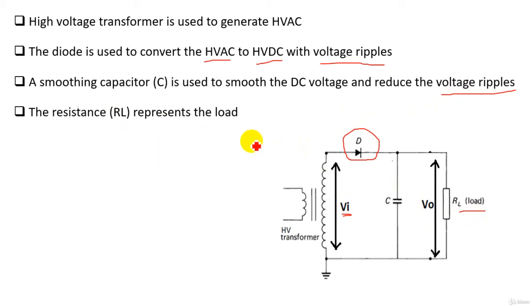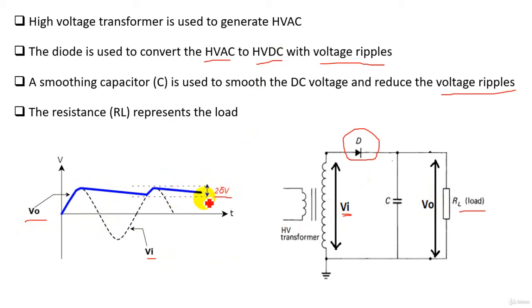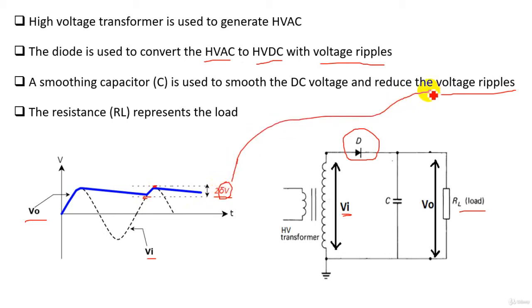The operation of this circuit is shown in the waveform. The input voltage — the secondary voltage of the high voltage transformer — is AC and sinusoidal. The output voltage is a unidirectional waveform, which can be considered as DC voltage with some ripples. The ripple voltage is the difference between the maximum and minimum output voltage, called 2·ΔV, where ΔV is the ripple voltage.